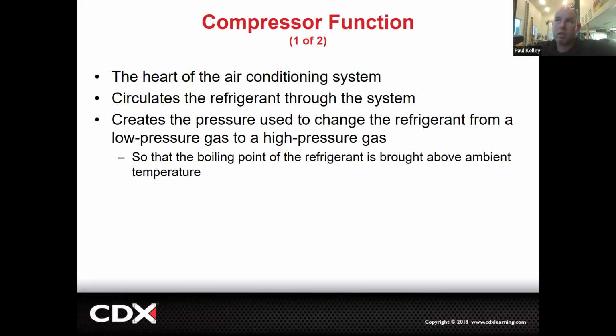Now, compressor. It's known as the heart of the air conditioning system. Why? Because it does what the heart does. It circulates blood or refrigerant, in this case. The compressor itself creates the pressure used to change the refrigerant from a low pressure gas to a high pressure gas. Whoa, remember that. It's all about the change in state. But the change in state is induced by the pressure, because remember, pressure changes boiling point.